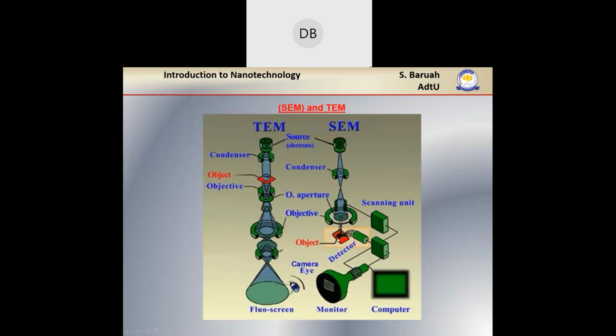So we scan the sample, and during the process of scanning, we are throwing out some electrons which are called secondary electrons, and we have a detector that picks up the secondary electrons. Now, actually, in a typical SEM, there are two detectors. One is inclined like this to pick up the electrons coming out at a slant, and there is one here also, actually. It is not shown here; it is shown as an aperture for passing the small beam of electrons. So just near the aperture, we actually have another detector. I'll tell you why we have two detectors in a scanning electron microscope.